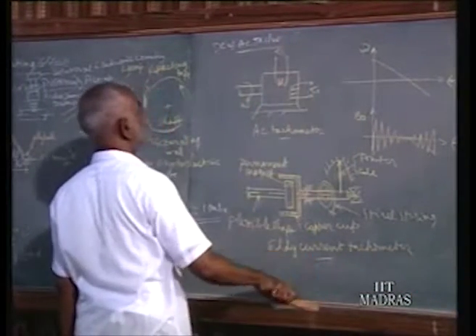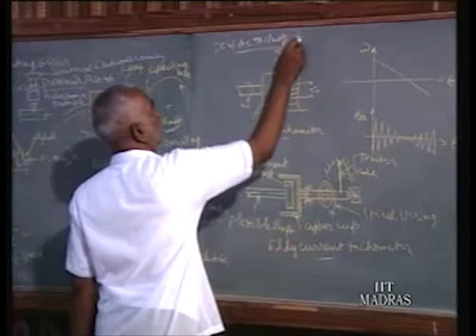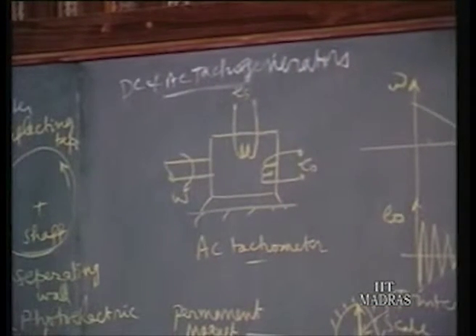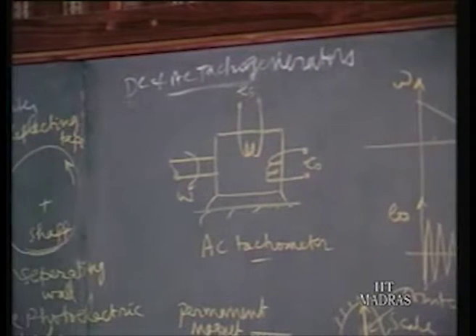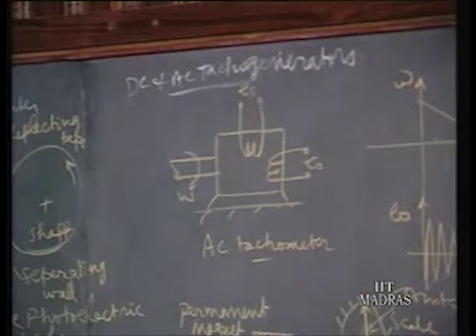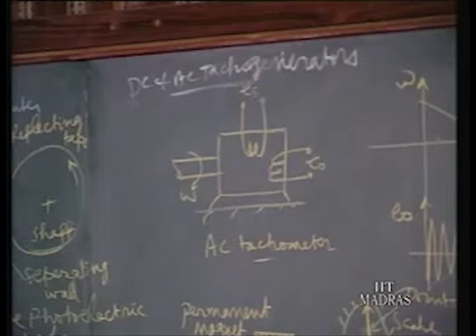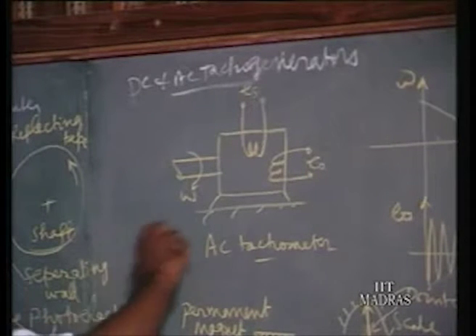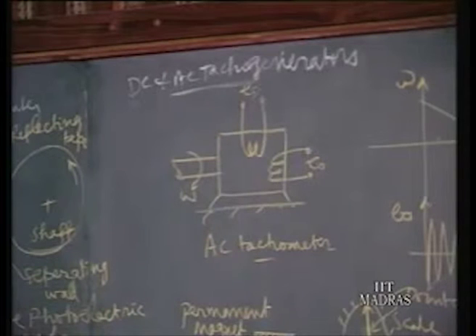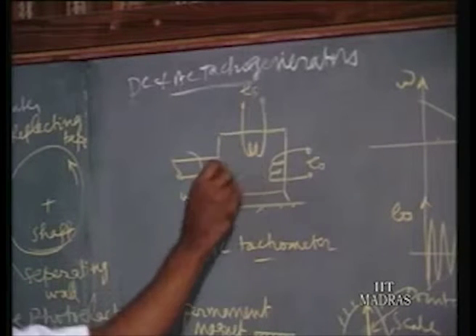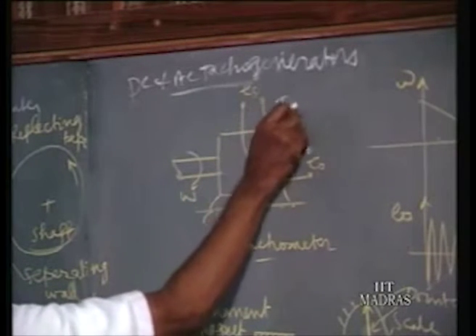Tacho generator, AC tacho generator. That is simple. An ordinary DC generator is used to measure the RPM of the rotor, because the voltage output, we know, is proportional to the RPM of the rotor. So voltage is calibrated in terms of RPM.